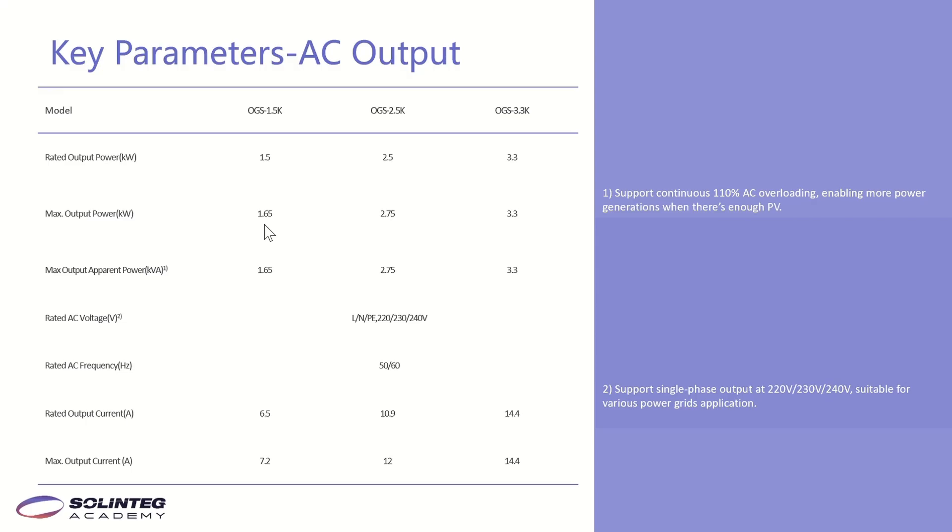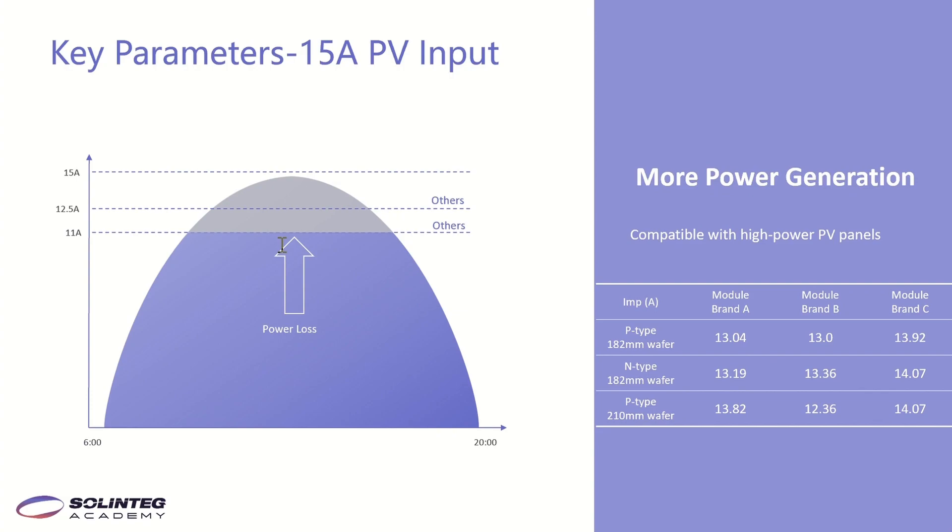This page shows the benefits of the 15A PV input for customers. Several brands of large-current PV panels have been evaluated — their current can reach 13A or 14A. If you use such panels with an inverter whose PV input is limited to 11A or 12.5A, the current will be clipped by the inverter, causing power loss. But with the Solinteg OGS and its 15A PV input, the full current of the PV panels enters the inverter — no power loss, no limiting.